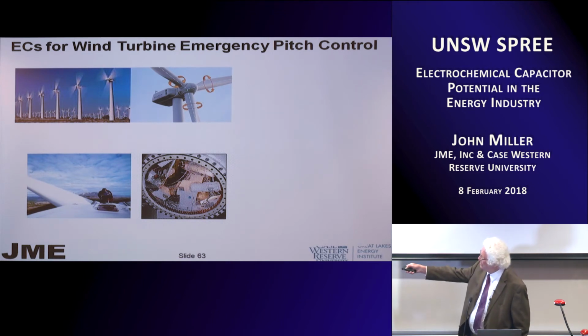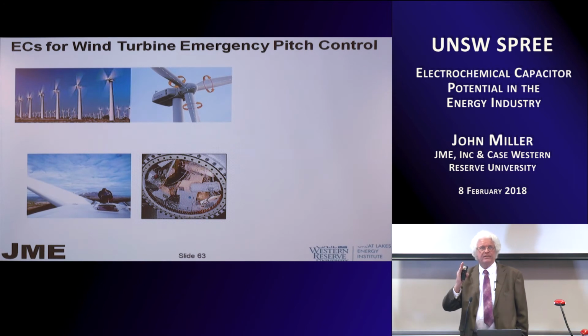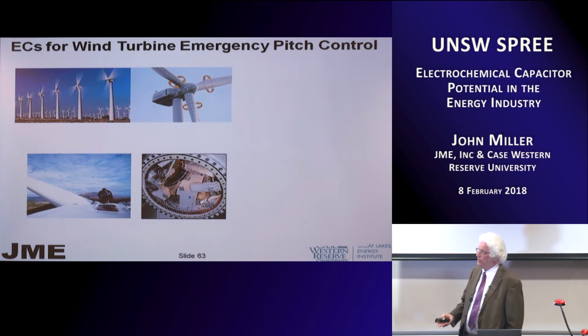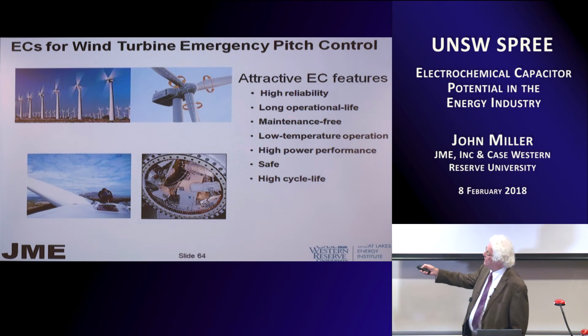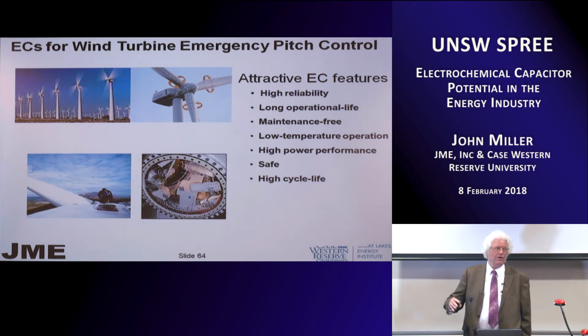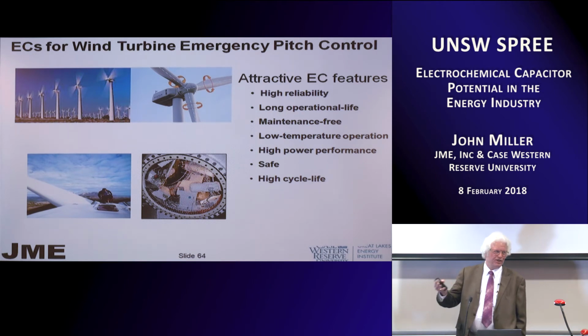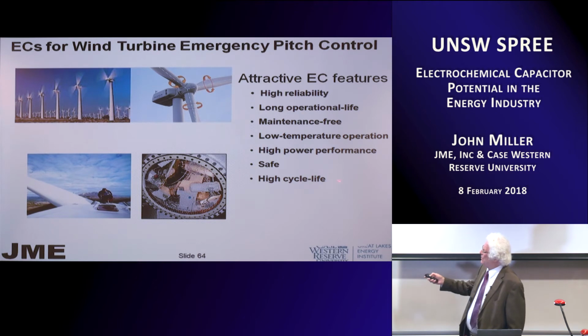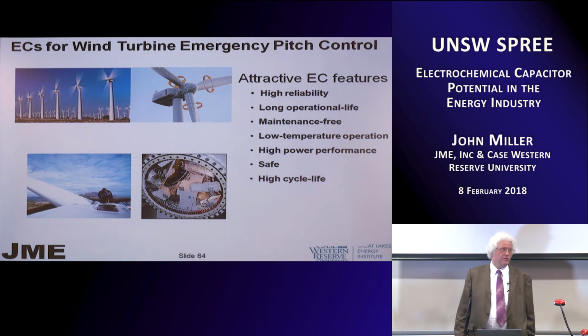In the hubs of these turbines, they have electric motors to feather the blades if they lose power in an emergency situation, using stored energy, and capacitors are very popular here because they're reliable, work at low temperatures, and have real advantages. They're maintenance free, and these towers are typically 100 meters tall or taller, so it's not a fun place to walk up to change batteries. They're also very safe with high power performance, and the motors typically are many horsepower for that emergency pitch control. This application in recent years has used a large volume of capacitors sold - it was one of the largest markets.